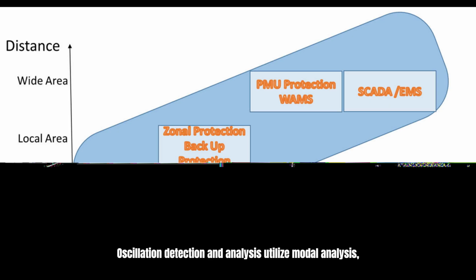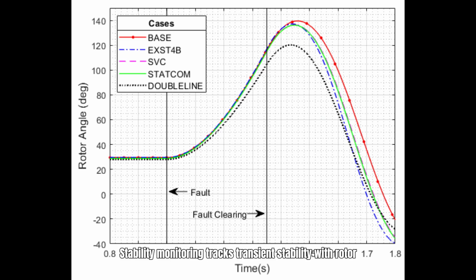Oscillation detection and analysis utilize modal analysis, such as the Prony method for modes between 0.1 and 2 Hz, and spectral analysis with FFT up to 10 Hz resolution for inter-area oscillations. Stability monitoring tracks transient stability with rotor angle swings below 180 degrees, voltage stability using PV curves, and frequency nadir, maintaining a minimum of 59.3 Hz post-disturbance.